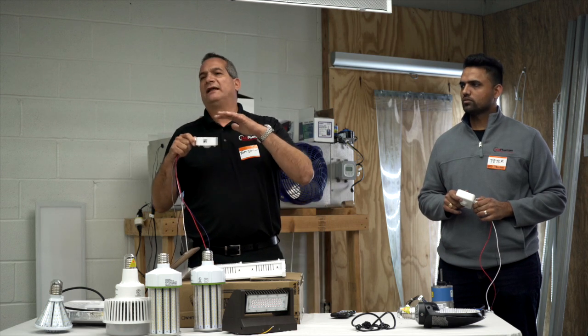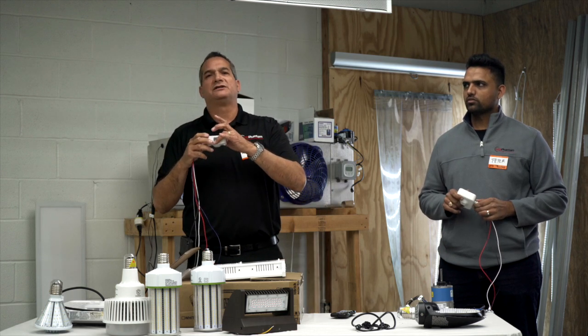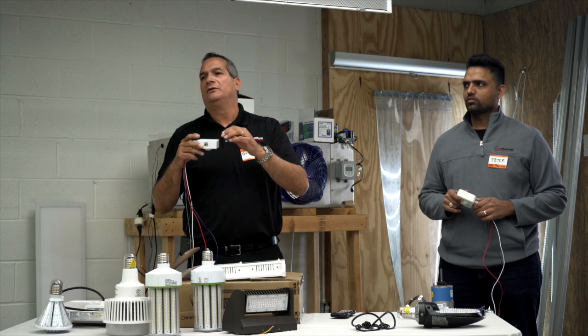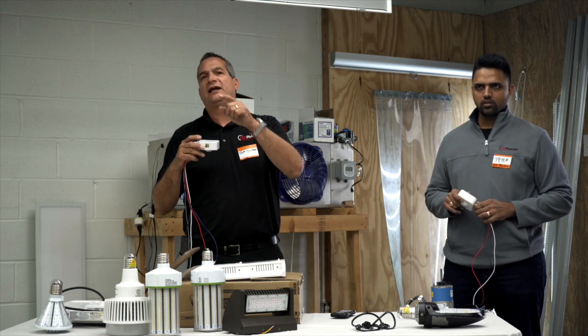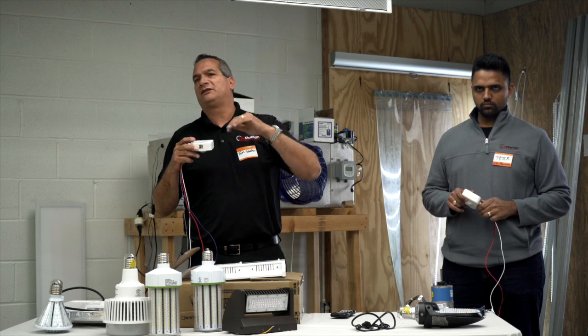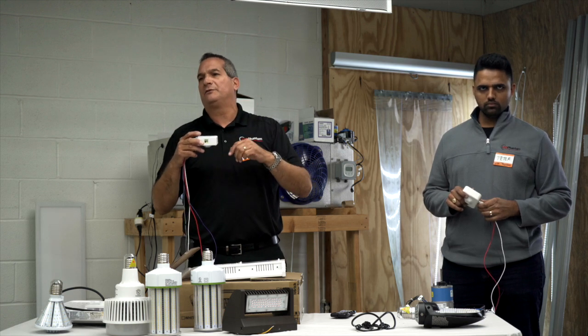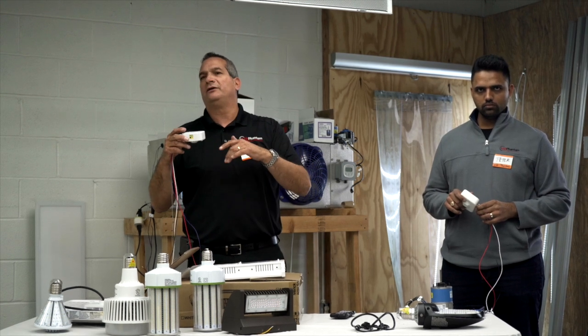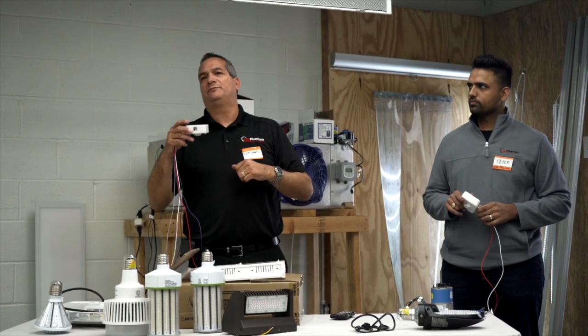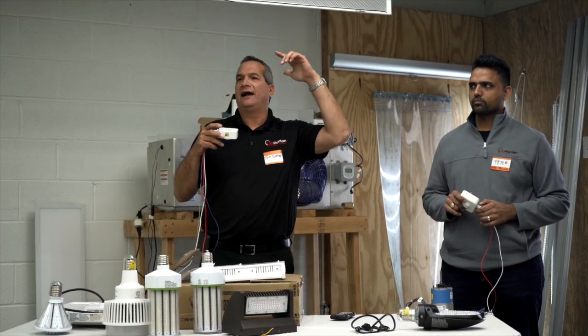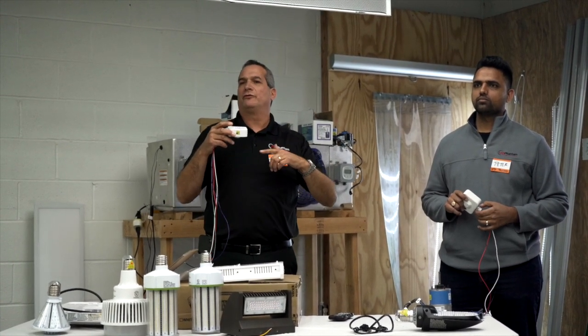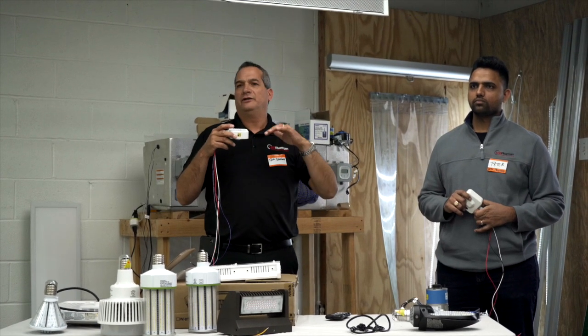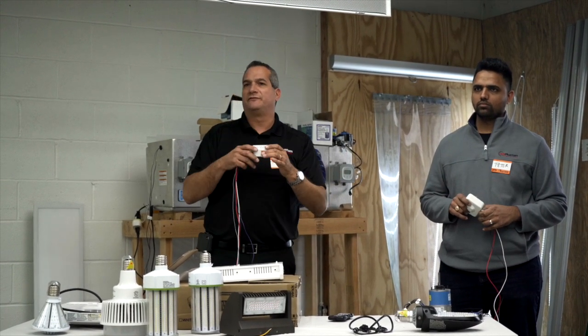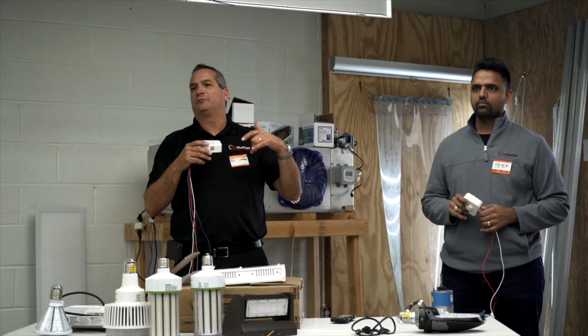What you can do with a bi-level dimming sensor is tell it, hey, I'm in a stairwell, I want to shut down but I can't shut off all the way, so only take me down to 30% when there's no occupancy. In fact, if it's bright in here, only turn me on to 70%. So you have control of the high range and the low range for on-off in the bi-level dimming, which gives you a lot of flexibility in your programming.